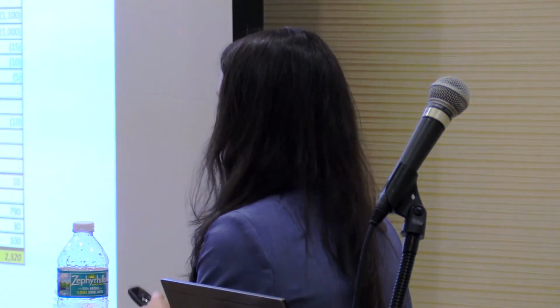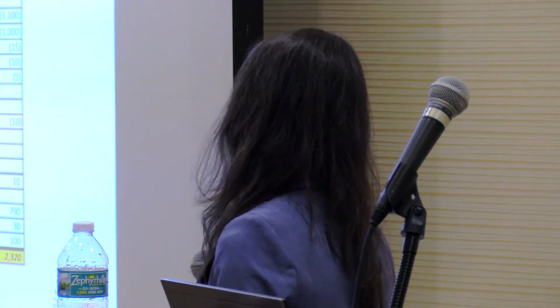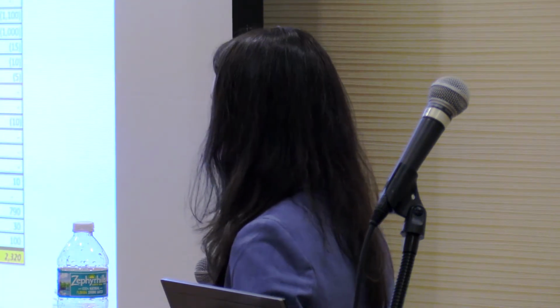And he handed over a report to us, and we actually took it upon ourselves to do a little bit of our own analysis. It's great to get a balancing report, it's kind of the raw data, but what we needed to do at that point was some airflow accounting, some basic, well, am I at least close? What I'm putting out, am I for the most part getting back? And as it turns out, the answer was no, especially on the return side, and I will go more into this later when we get to the findings section. But we were quite short, actually, on the return side, which was made apparent by this balancing verification.